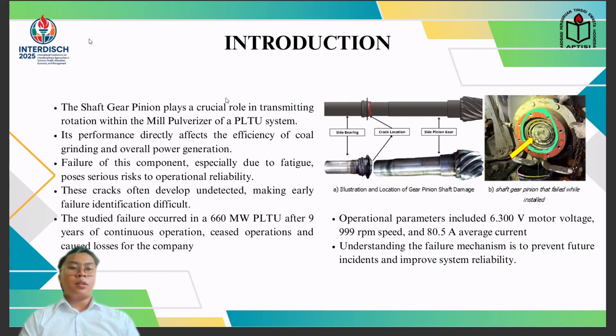Okay, introduction. The shaft gear pinion plays a crucial role in transmitting rotation within the Mill Pulverizer system. Its performance directly affects the efficiency of coal grinding and overall power generation. Failure of this component, especially due to fatigue, poses a serious risk to operational reliability. Cracks often develop undetected, making early failure identification difficult.